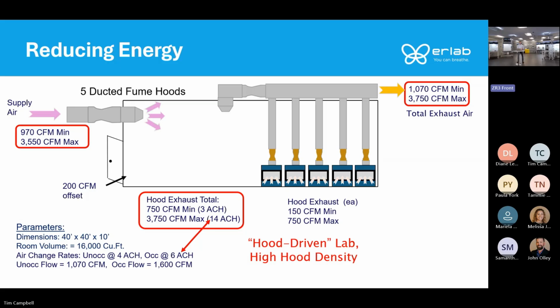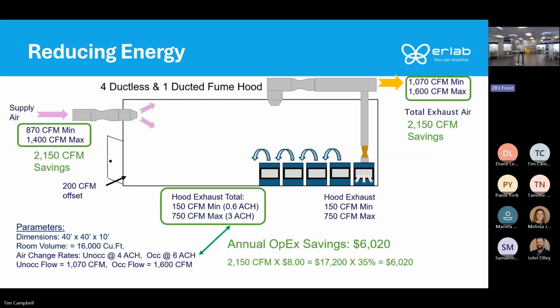Now we take that same example and we go with 4 ductless fume hoods and 1 ducted fume hood. Now with 1 ducted fume hood, you're only going to use 750 CFM, which is well below the 6 air changes per hour that you need. So overall, you'd have about a savings of $6,000 per year based on 35% use throughout the week or throughout the year. And that's because the ductless fume hoods are not part of the HVAC system. They are not exhausting any of that air outside.